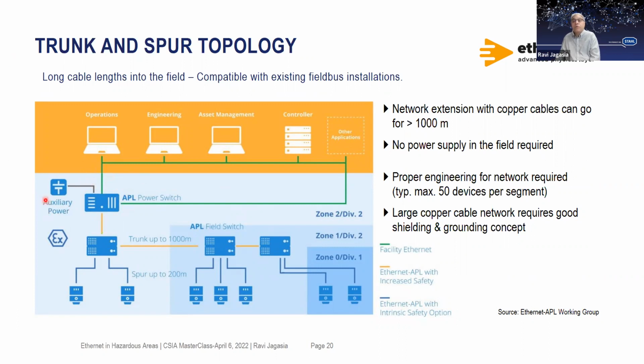The power switch is sourcing the power, just like the fieldbus power supplies of the foundation fieldbus architecture. And then it is driving the two-wire intrinsically safe power into the field. This trunk allows you to run 1,000 meters. And then you have the field devices in Zone 2, Div 2, Zone 1, Div 1, and all of them connected through the field switches into the power switches and then to the Ethernet APL connection cards.